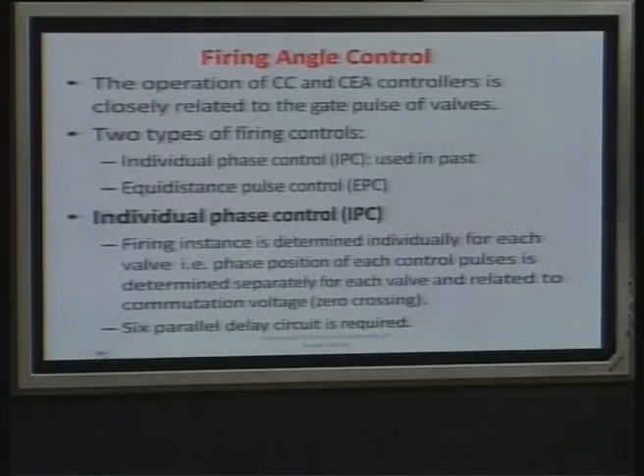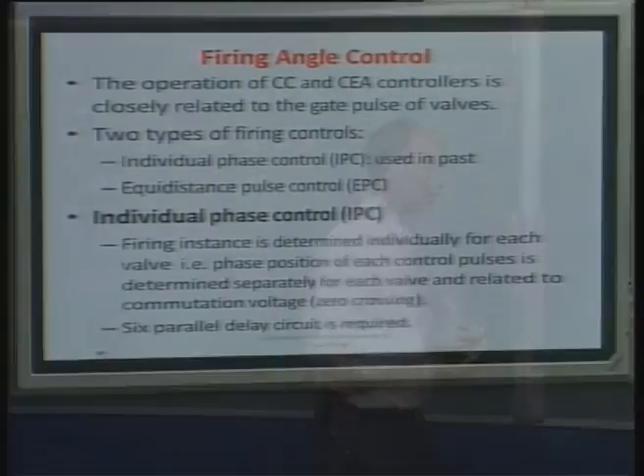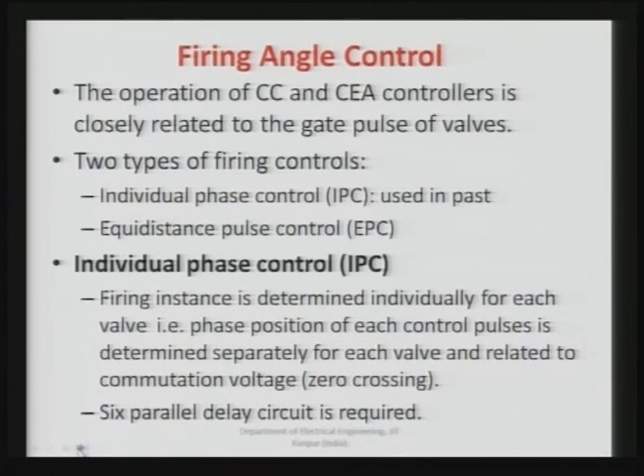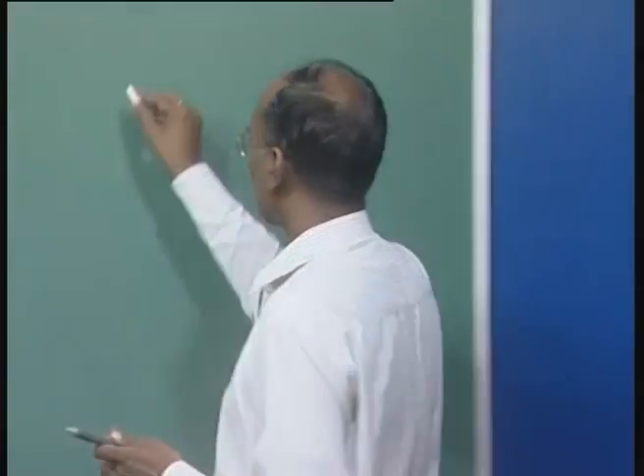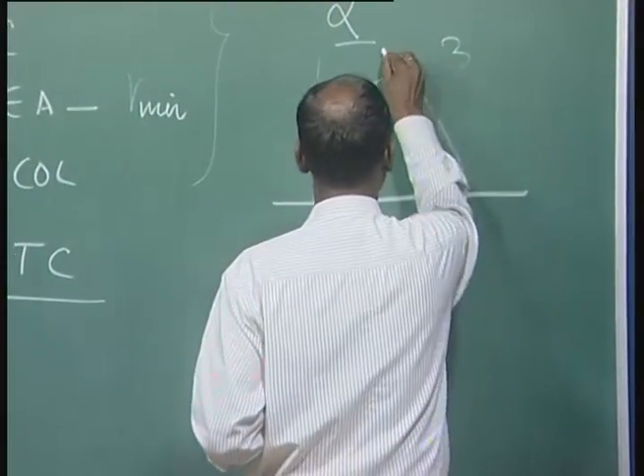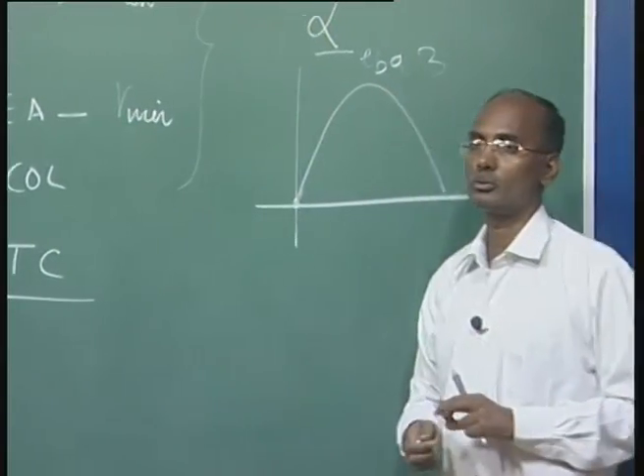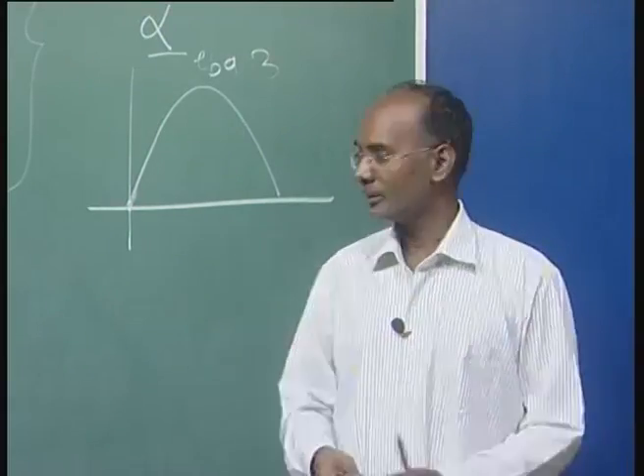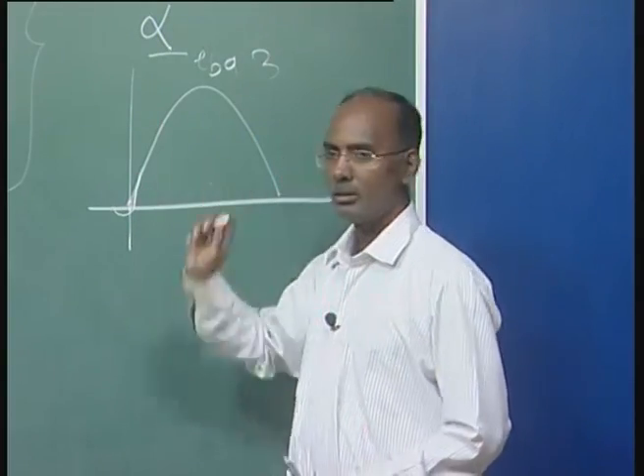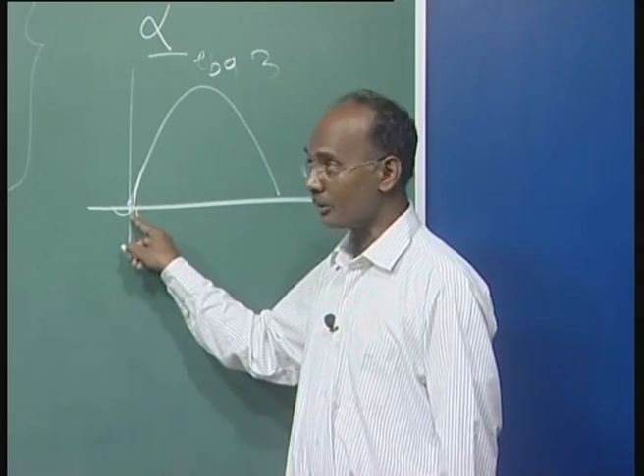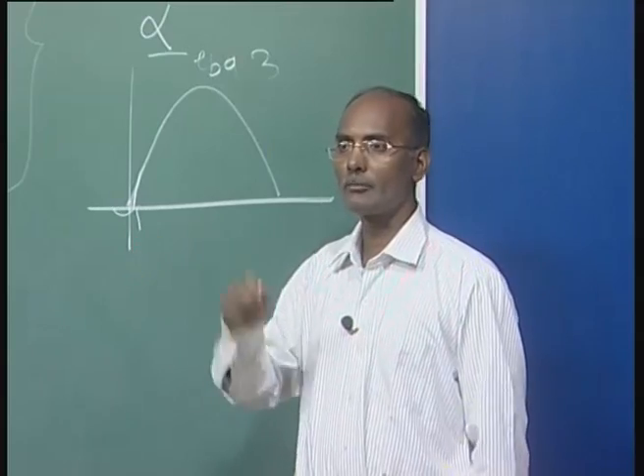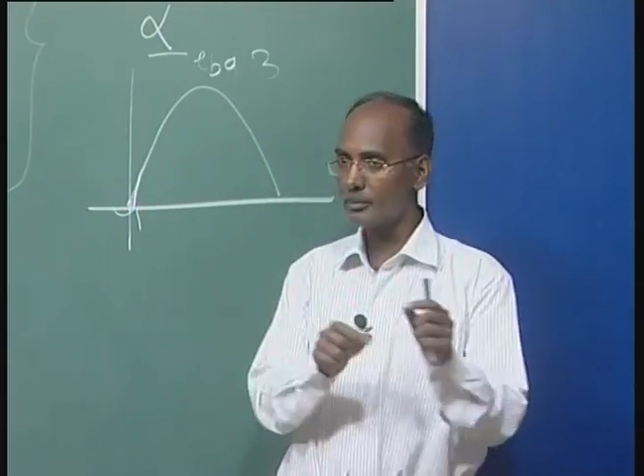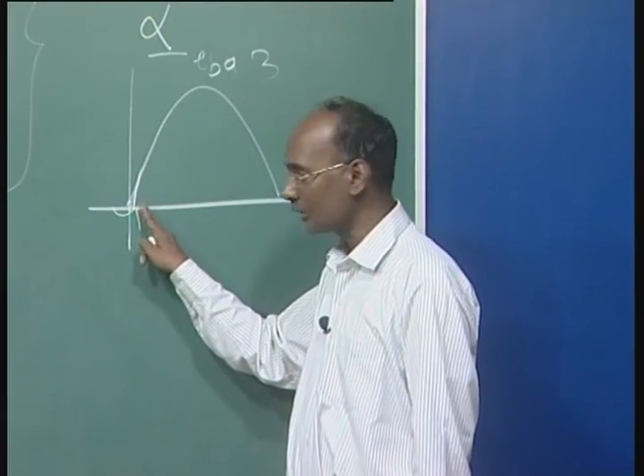In individual phase control, the firing instant is determined individually for each valve — the phase position of each control pulse is determined separately, that is alpha 1 to alpha 6 for each valve — and it is related to the commutation voltage. The commutation voltage, for example of valve 3, is E_BA, and its zero crossing needs to be known. There is also a problem: if using zero crossing, due to some distortion or fault, this zero crossing may shift, causing alpha to change.